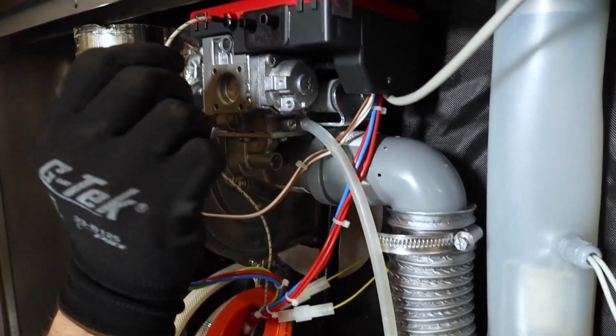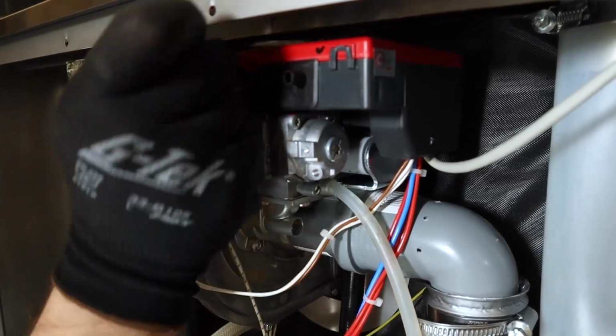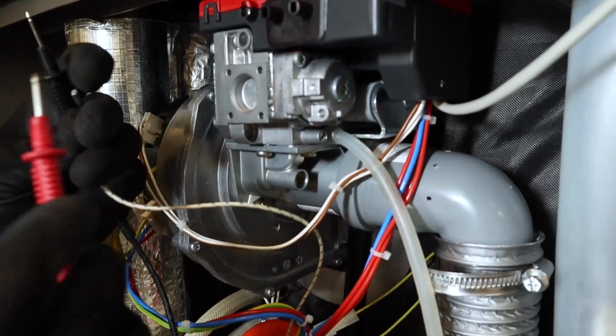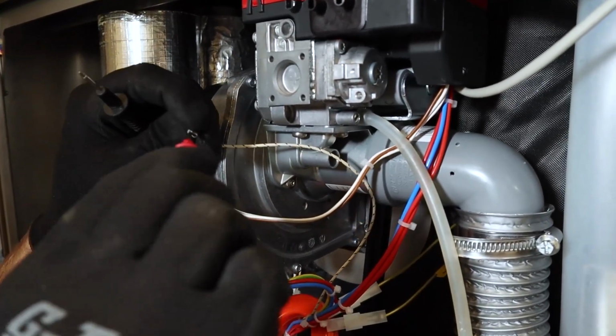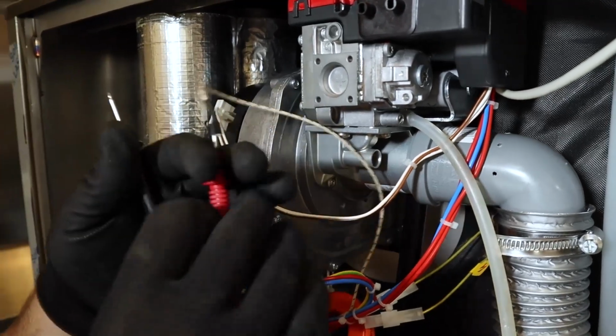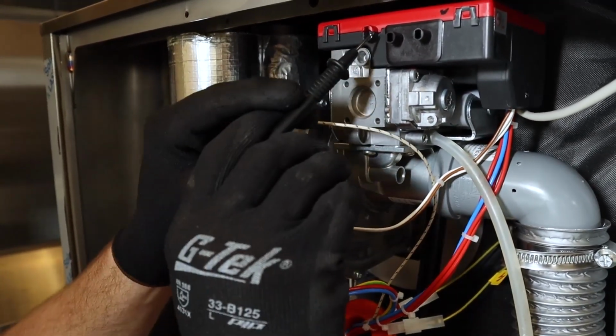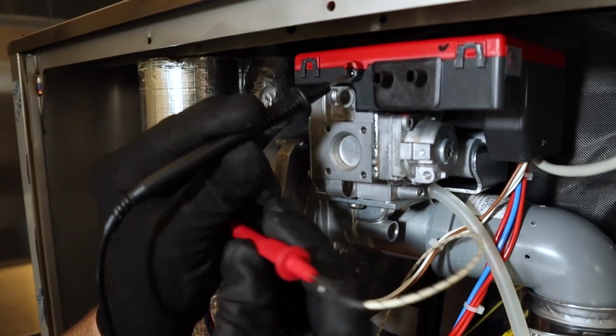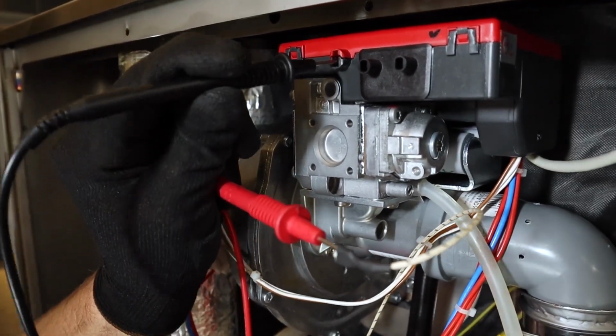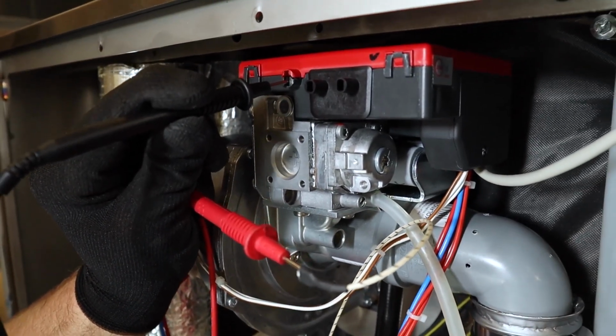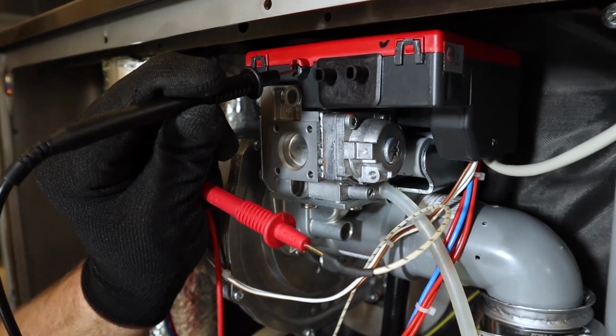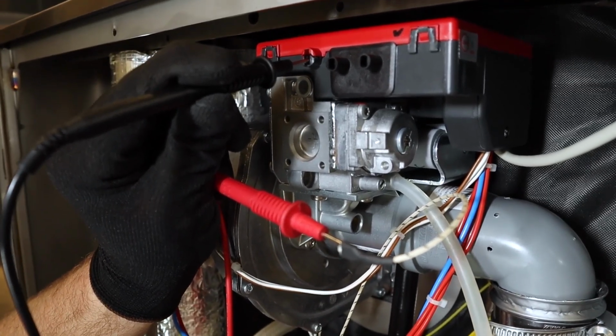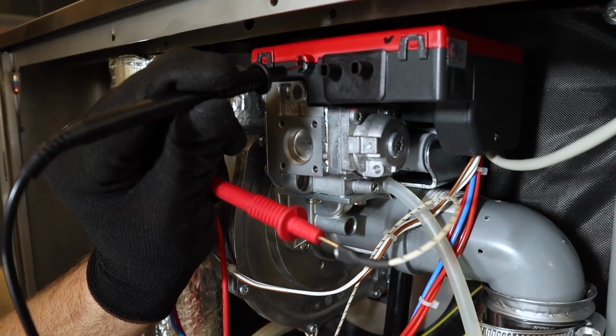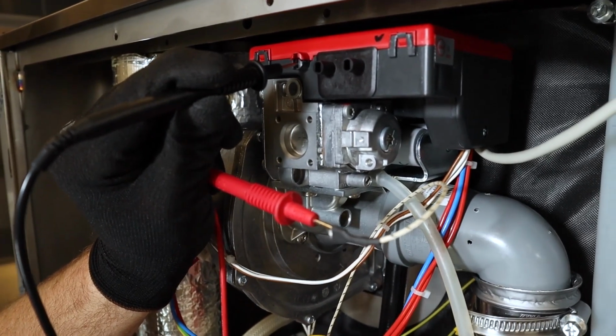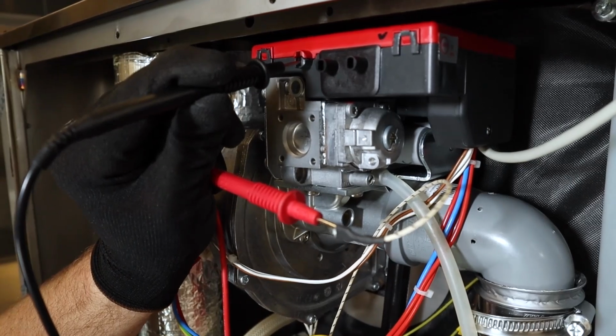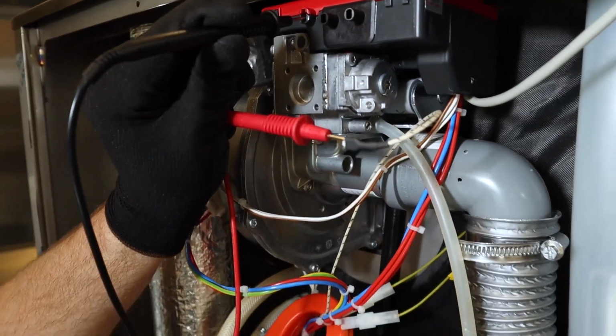Now we'll come right here to our flame sense wire on the ignition module. I'm going to go ahead and unhook that. I'm going to stick one meter lead in one end of my flame sense wire, and then I'm going to put the other meter lead right in my connection right here at my ignition module. Now this is where I'm going to go ahead and start a cook cycle from the front, and I can check my gas pressure as well as my microamp reading at the same time. Now for microamps, we're looking for at least 3 microamps on the flame sensor.